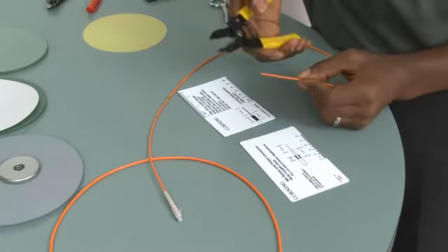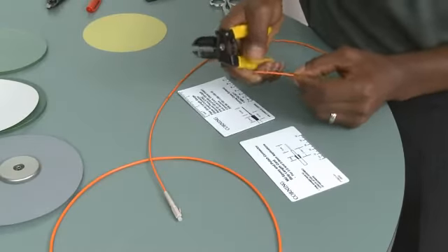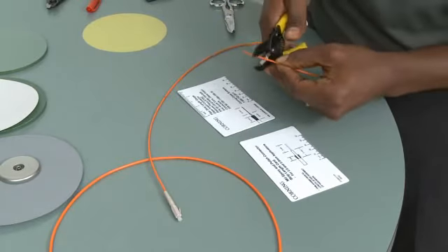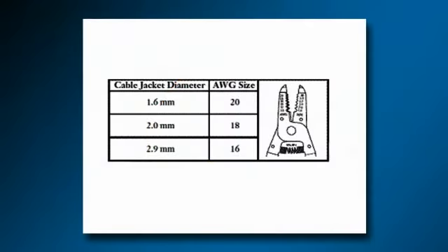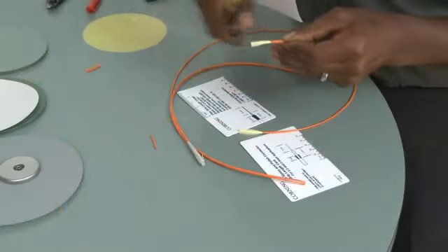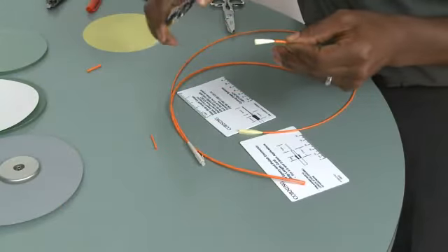Using a buffer stripping tool, remove the jacketing at the mark closest to the end of the jacket. For 1.6 millimeter, use the 20 gauge, and for the 2 millimeter, use the 18 gauge, and for the 2.9 millimeter, use the 16 gauge. And then remove the jacket with no sliding motion, you may damage the fiber on the inside.